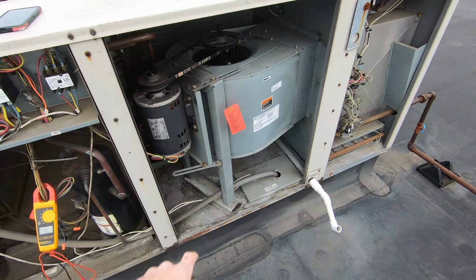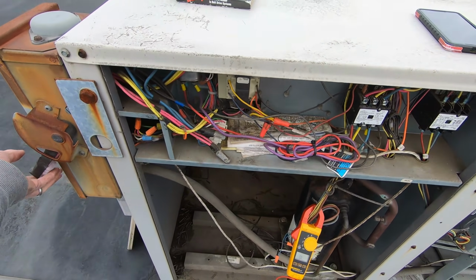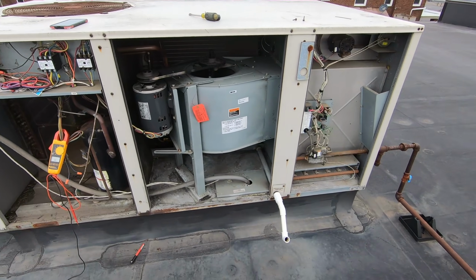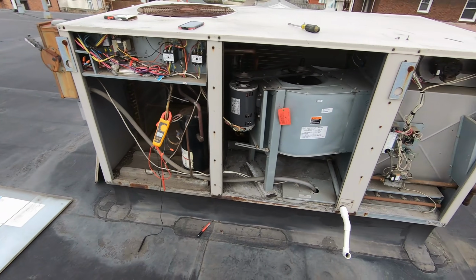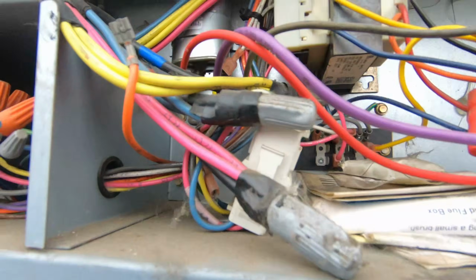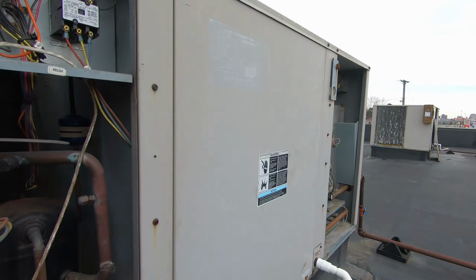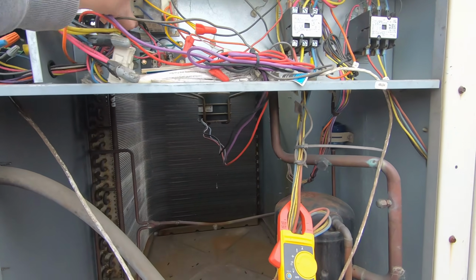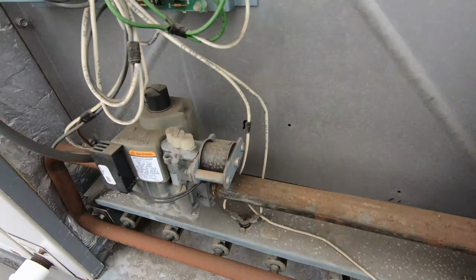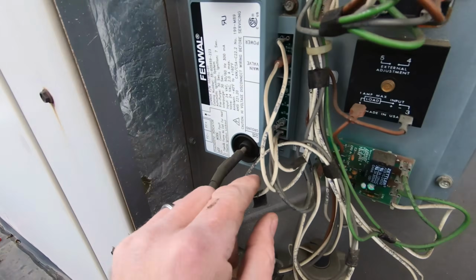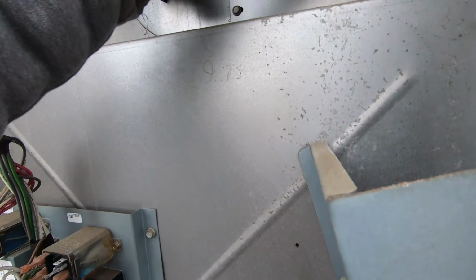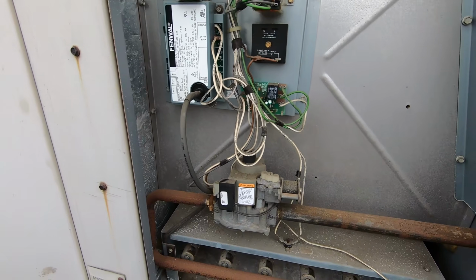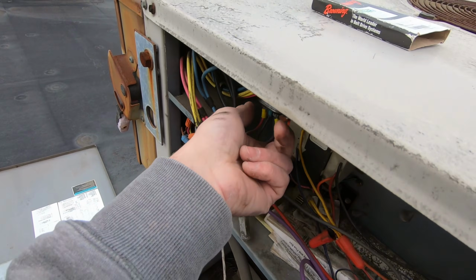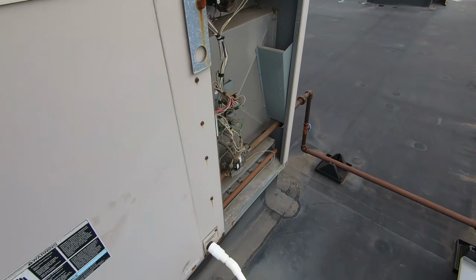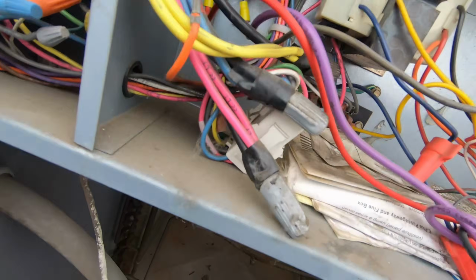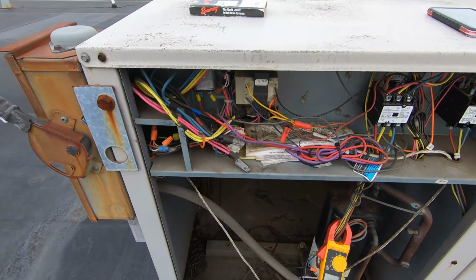All right, I got all my info on the blower. I got the belt back in place. I've got my little 3 amp circuit breaker replaced. Hey, there we go. Got a blower now. I'm gonna get that panel put back on. I'm gonna cycle it in heat, see if we trip that 3 amp fuse. And we tripped. Seemed like as soon as everything tried to come on the heat end, it tripped it. Go start investigating over here, see what we got going on. But yeah, as soon as the combustion blower kicked on and everything tried to kick on over here, it kicked that 3 amp fuse off. And it's now just continually popping the 3 amp fuse.